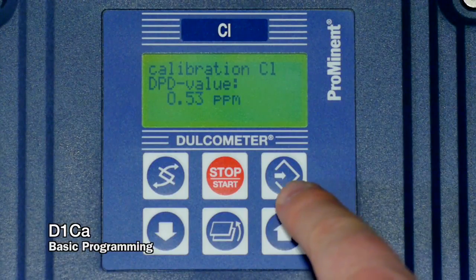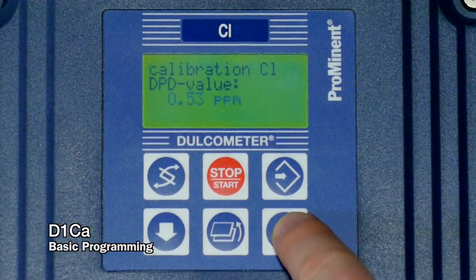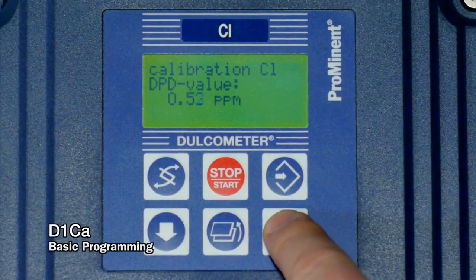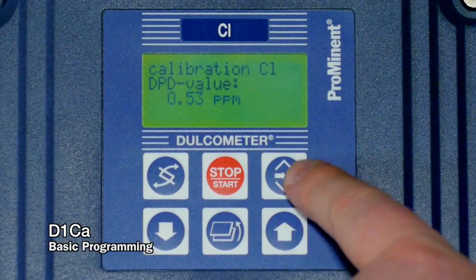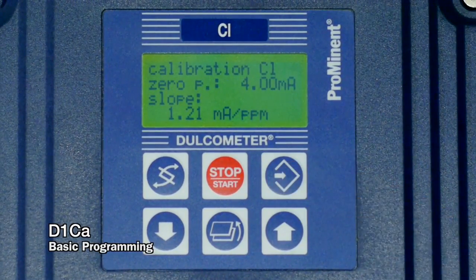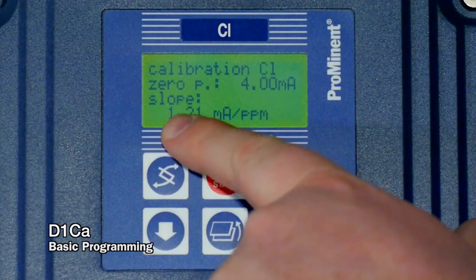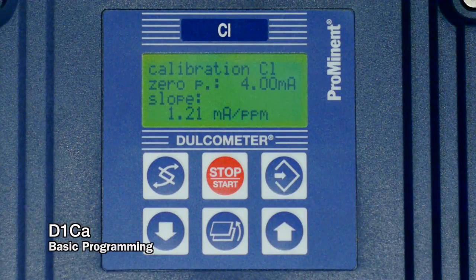So it's important to grab that sample as close to the point in time as we go into this menu as possible. Once we do our calibration and we get the value from our measurement, we can hit the up or down arrow button again to dial in to what it should be according to that measuring device or process. If it's DPD type, we hit the enter button and it's going to come back and tell us what the slope equals according to what it's measuring and what we tell it that measurement is equal to. That slope will then be applied to that measurement and display whatever the result is. That slope is a calculated value. You cannot change it physically. It's a calculated number based off of what it's measuring and what you tell it's equal to with your calibration.